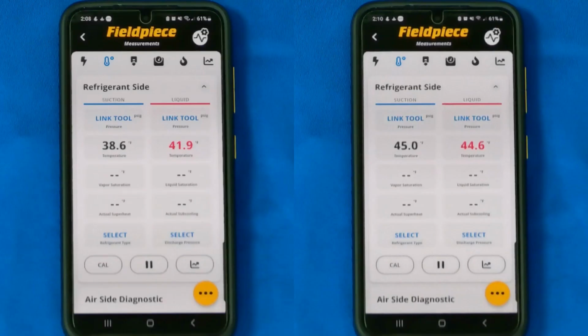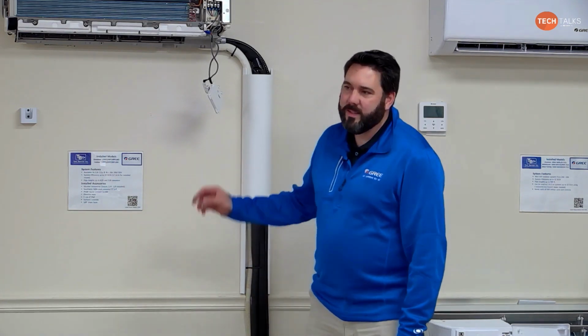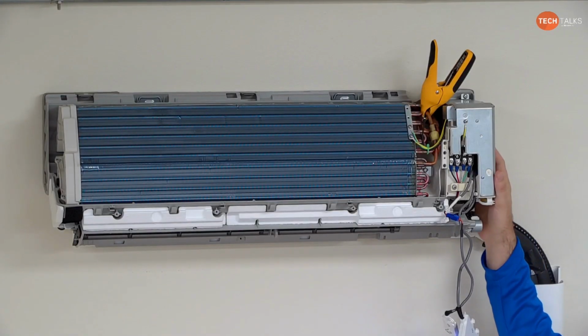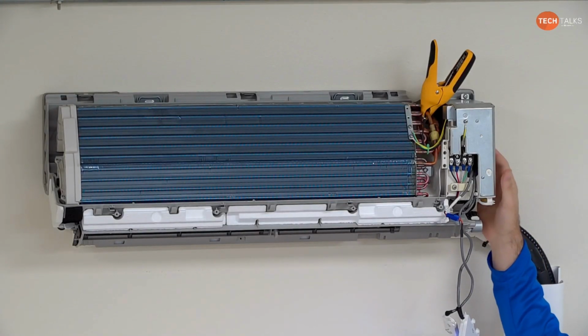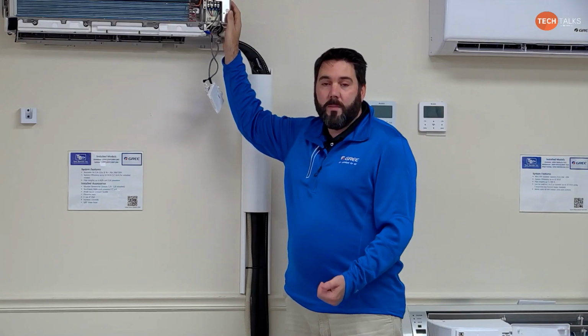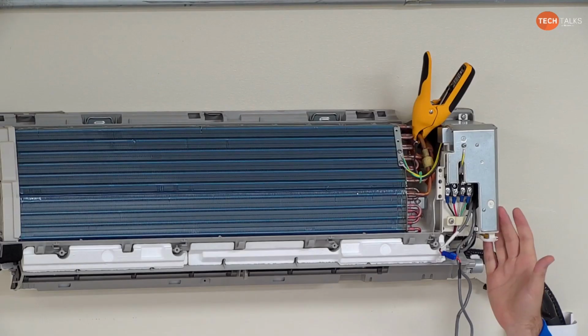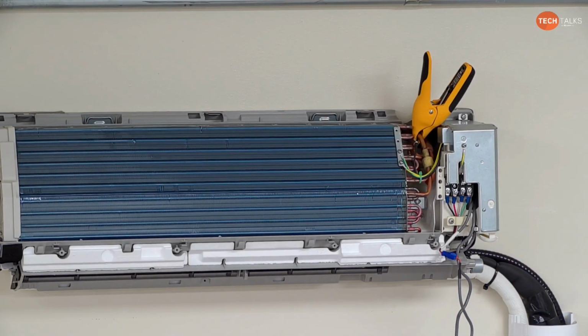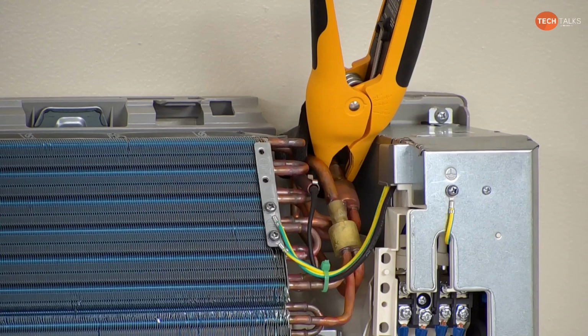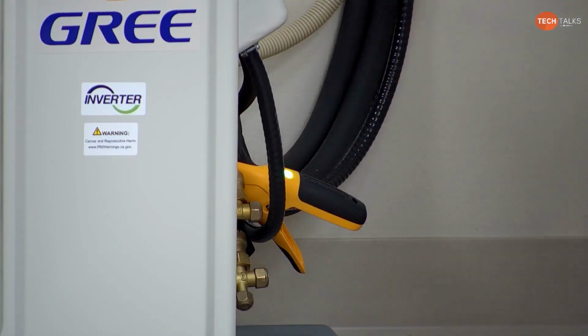Always remember that when we're troubleshooting a refrigerant circuit, always track your temperatures of your refrigerant. Don't forget that with any GREE mini split product, the line set is an extension of the indoor coil. So in the cooling mode, it acts as the evaporator, and in the heating mode, it's acting as the condenser. The reason that we refer to it as suction and liquid is that's just what we're used to, but it's actually a gas line and a flash liquid line, basically. So that's how you do the 4-point temperature check.